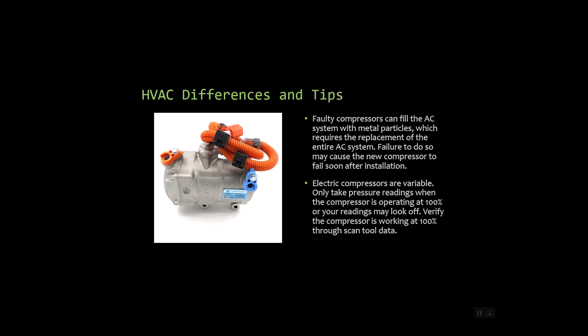Generation 2 compressors have 3 power wires because they are 3-phase. So it gets a three-phase voltage from the inverter. Since our battery is direct current, it has to change to that 3-phase through the inverter and get sent down to the compressor via 3 different wires. Generation 3 compressors are 2-wire and use a nominal 201 volts directly from the battery. So that's direct current directly from the battery.